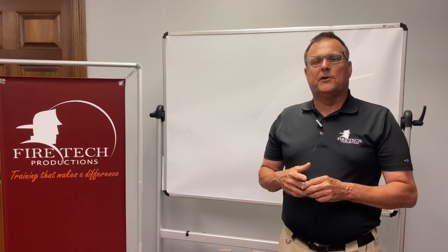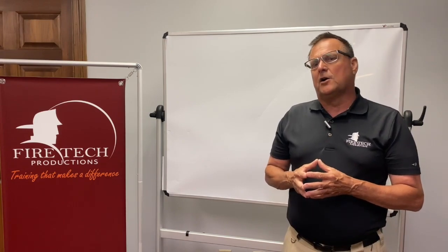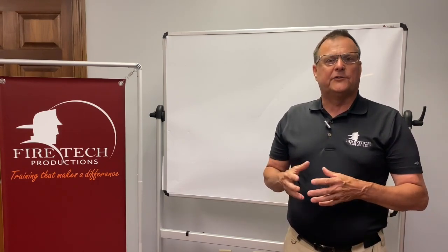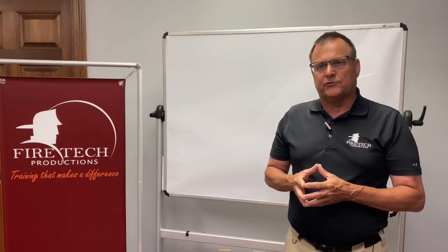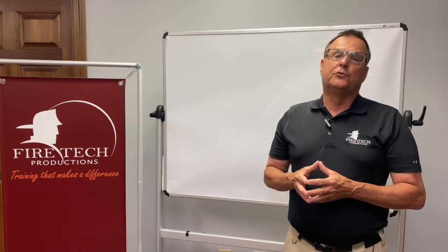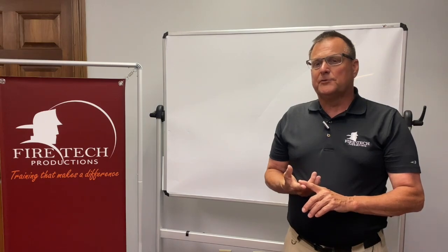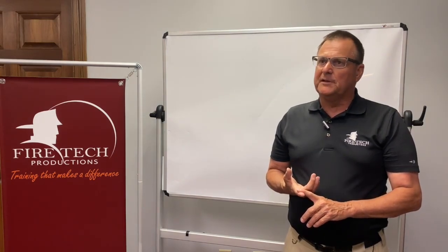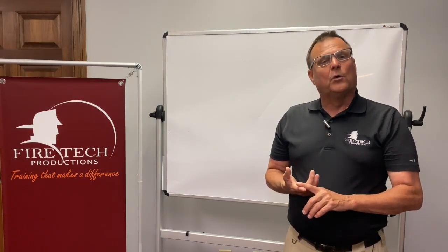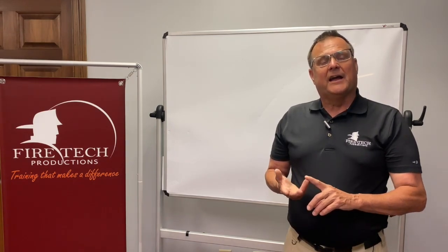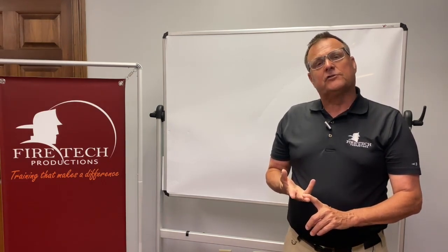Is it a business building? For example, there are not a lot of requirements for fire alarm and detection in low-rise business use buildings in the International Building Code. But if you get into a residential occupancy, now you're going to find a lot more requirements because of the principal threat of people sleeping in residential occupancies for smoke alarms and for fire alarm and detection systems.